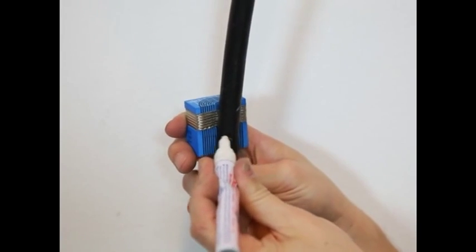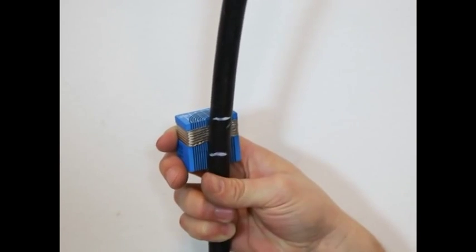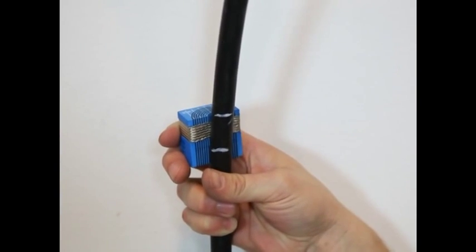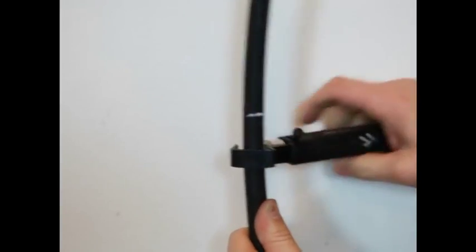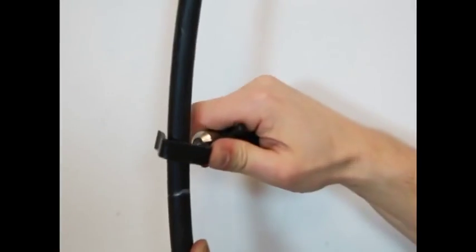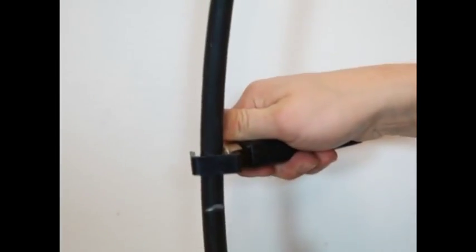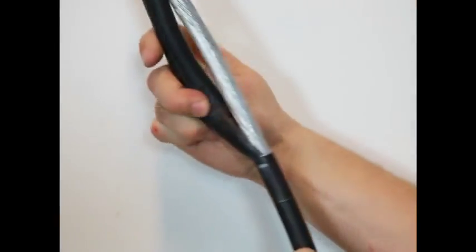If you intend to finish the armor with cable sheath, make two marks on the cable, corresponding to the braid section of the module, and cut the outer sheath at both marks. Save the short piece and remove excess sheath.